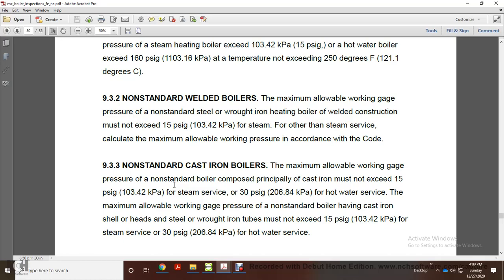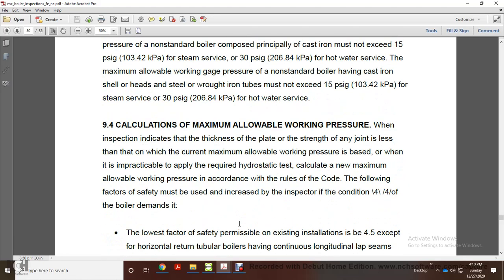9.3.3 Non-standard cast iron boilers. The maximum allowable working gauge pressure of a non-standard pressure vessel composed principally of cast iron must not exceed 15 psi gauge for steam service and 30 psi gauge for hot water service. The maximum allowable working gauge pressure in a non-standard boiler having cast iron shell heads and steel or wrought iron tubes must not exceed 15 psi gauge for steam pressure and 30 psi gauge for hot water pressure.